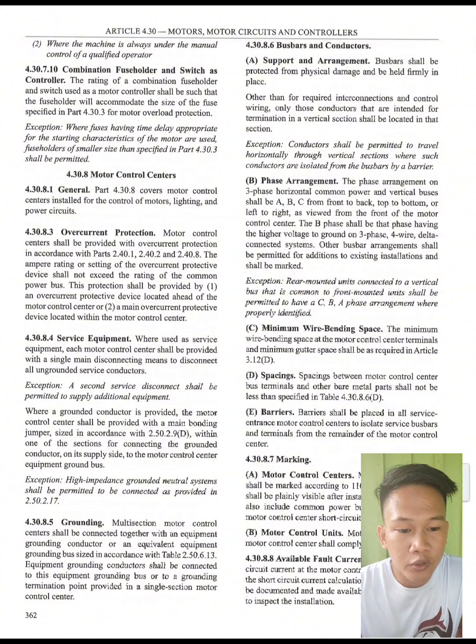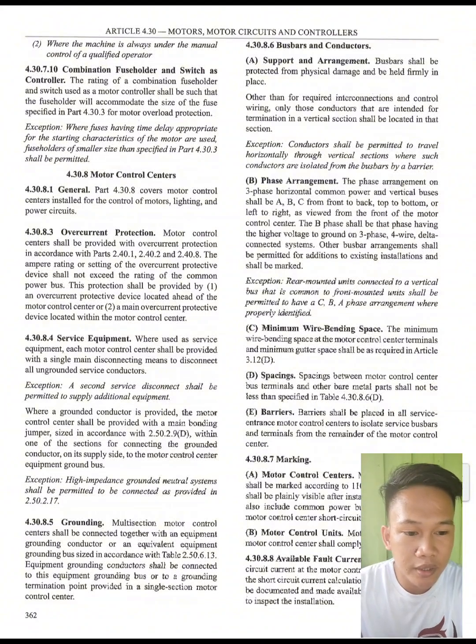So next is 4.30.8.8 Available fault current. The available short circuit current at the motor control center and the date the short circuit current calculation was performed shall be documented and made available to those authorized to inspect the installation.